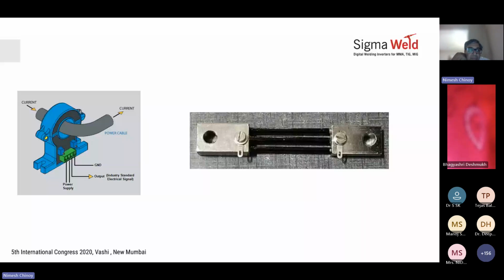So if you are welding at 400 amps, you can use a 400 amp CT. It will go from 0 to 400. You can have a 600 amp CT, which goes from 0 to 600. You can have a 1000 amp CT, which goes up to 1000 amps. And then you can use a 2000 amp CT for between 1000 and 2000 amps. So there are CTs available, and these are either split core or hollow core, so you can push a conductor through the same.